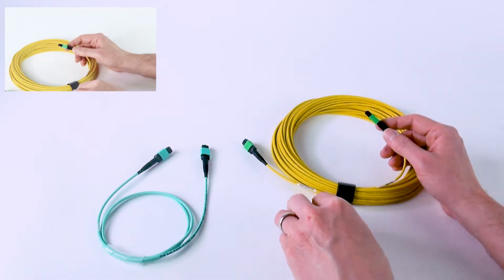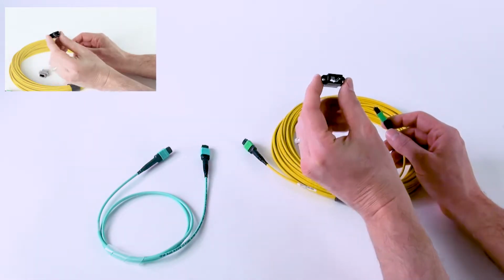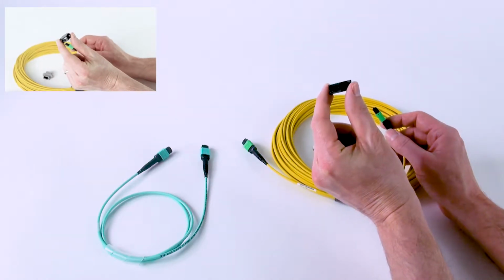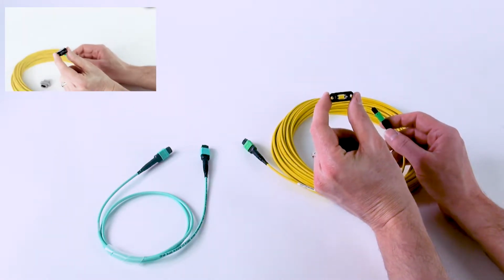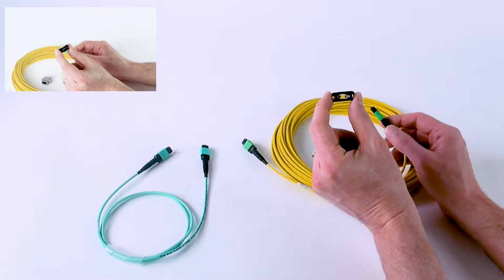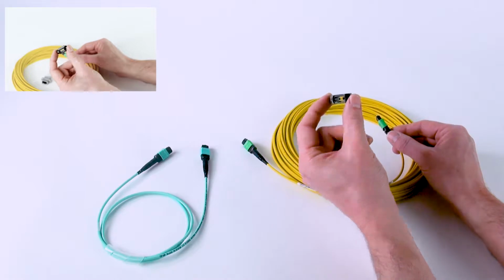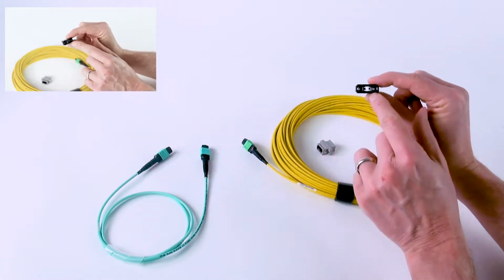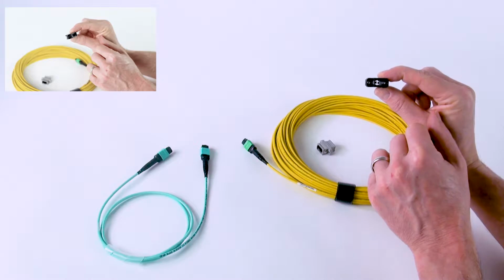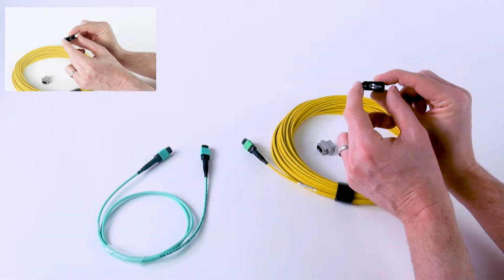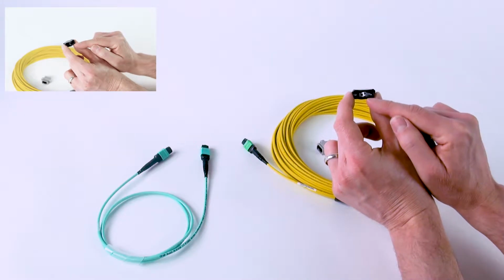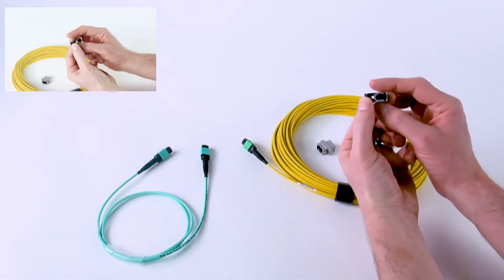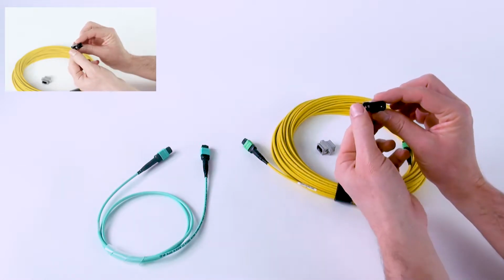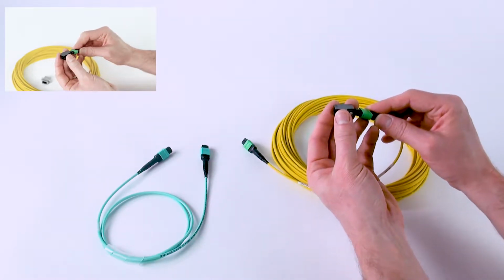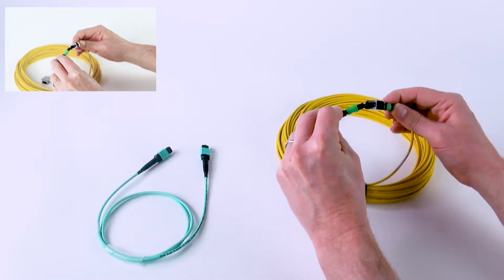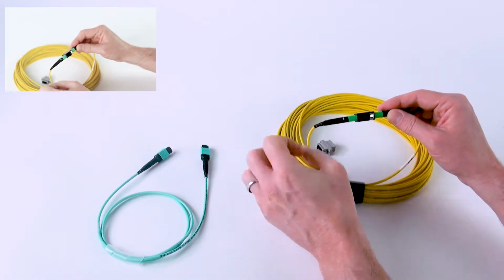With MPO connectors, they'll always connect through this very simple, large adapter block. With a single fiber connector, you're dealing with a precision alignment sleeve and such, but with MPO connectors it's very simple—you'll notice a notch that indicates the direction of the key. This is a common configuration where one side has the key down, but if I turn it over, the other side has the key up. So when these two are mated, one is key up and the other is key down, and that determines the polarity.